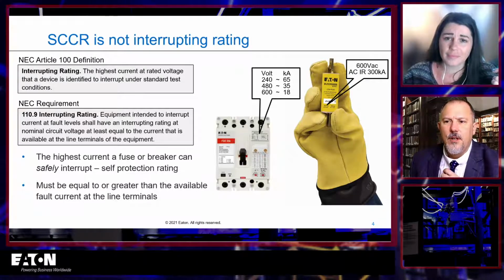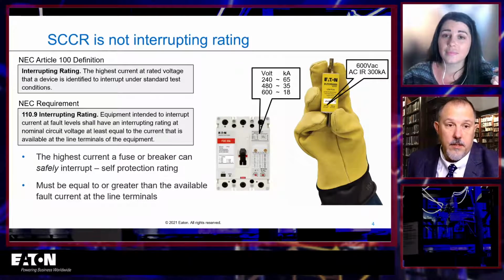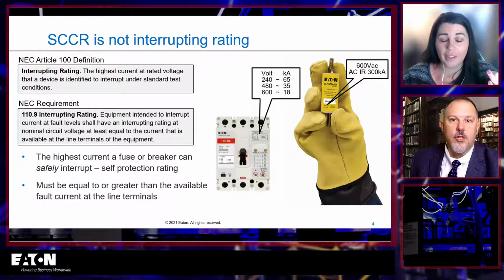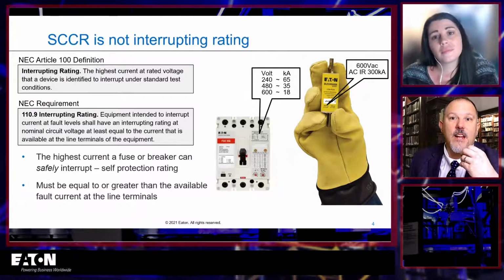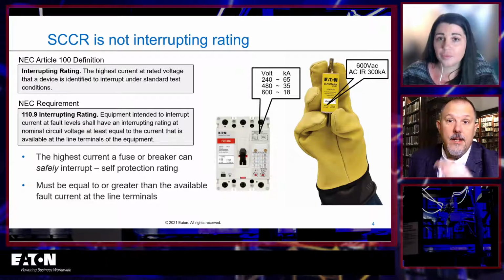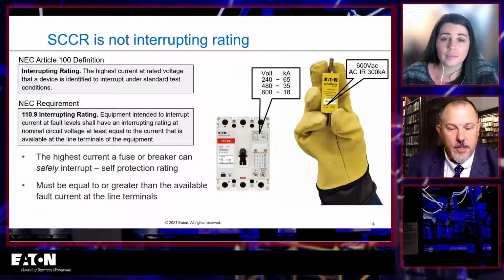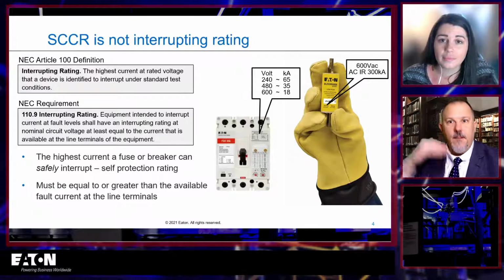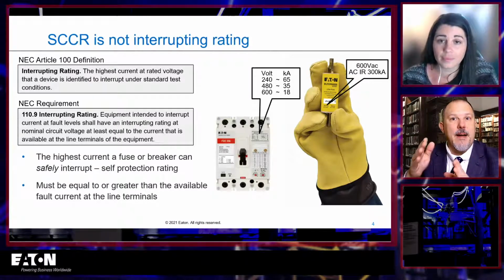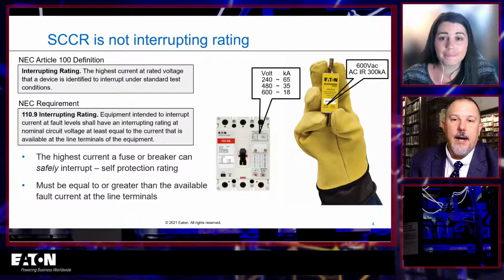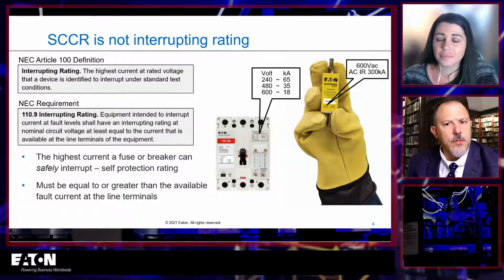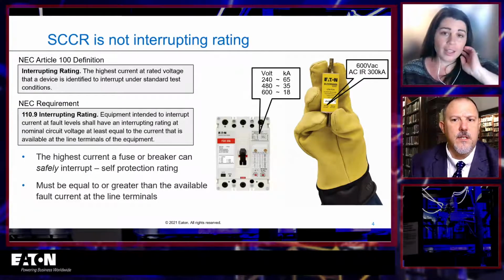When it comes to ambient temperatures, I think ambient temperatures are more critical when it comes to overloads and things like that, more so than the short circuit, because the magnetic forces of fault current is what drives that device to open, whether it's a breaker or a fuse. Not necessarily. Now, in the overload region, I know on breakers, they'll have ambient on the trip curves because in some cases, my bimetal inside of that breaker may be moving. I don't know as much of the impact on a fuse. I don't think it's as significant on a fuse as it is on a breaker.